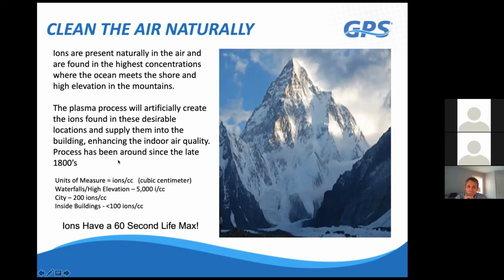And when these ions are generated, you have up to 60 seconds for them to react with something in order to control particulate or kill pathogens down in your space. We always recommend mounting these devices after your particle filters so they can treat further downstream.